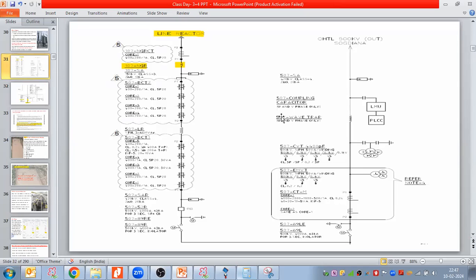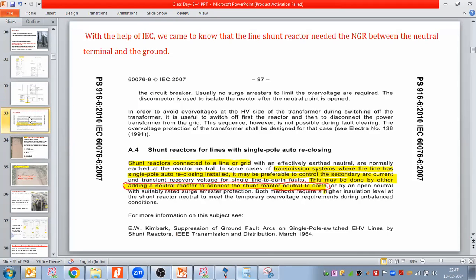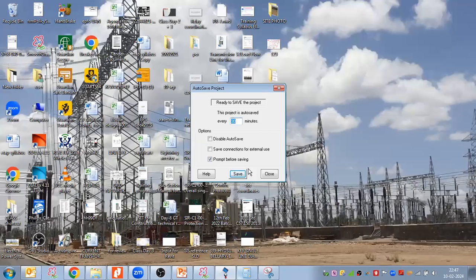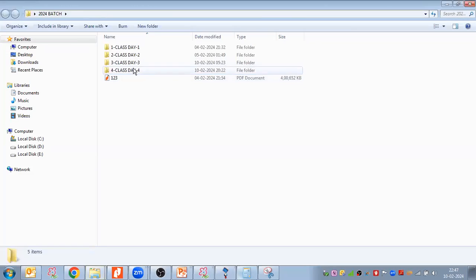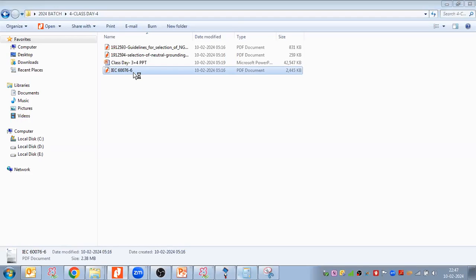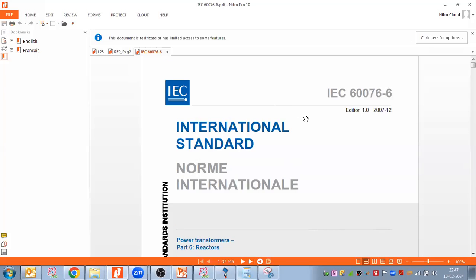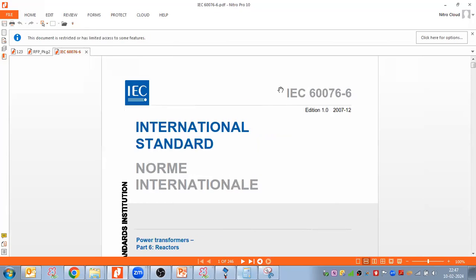So for this NGR, why it is required, there are two things that we should refer. The first thing is that I took the reference of IEC 60076 part number 6, page number 97. IEC 60076 is the standard for the power transformer. Reactor comes in the family of the transformer. Due to that reason, this 60076 is applicable for the reactor also.